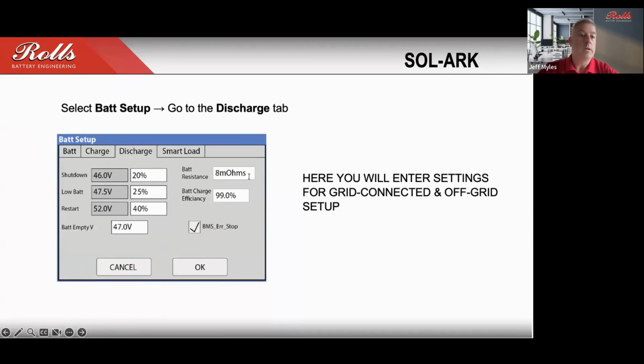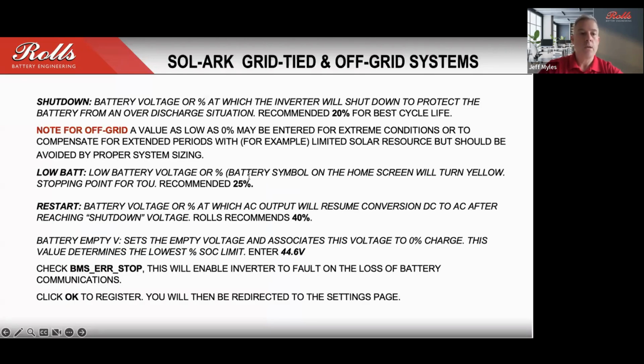These conditions are what we have recommended in the system. You may, in some cases, want to set these higher depending on the particular application, or depending on how you choose to set up the system. But we would not recommend going below those percentages just because it's most likely going to trigger a BMS condition to shut down the units.